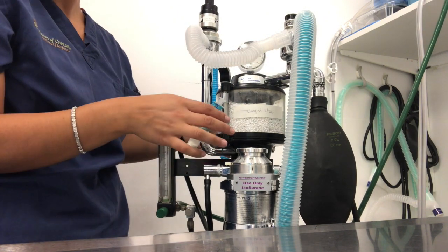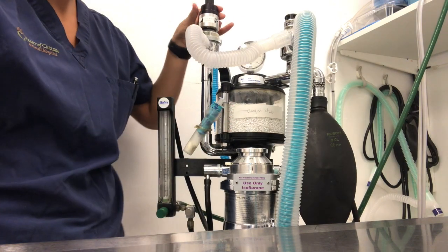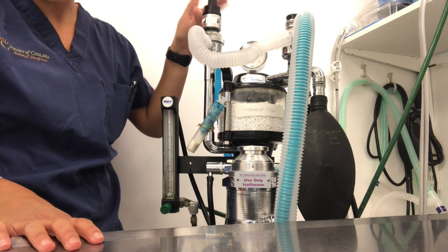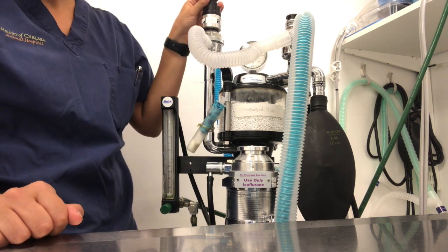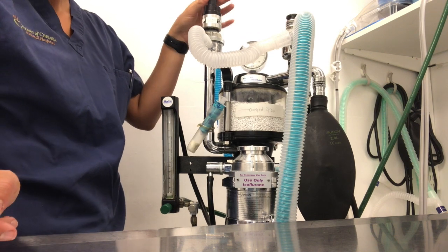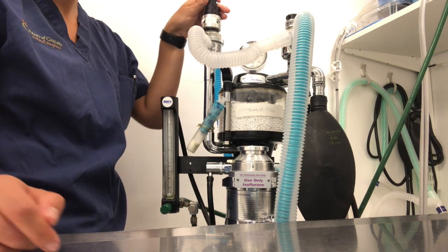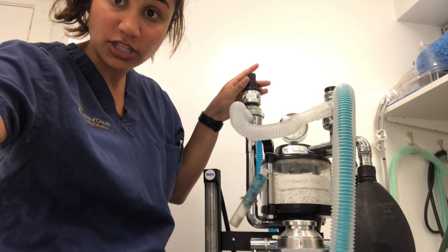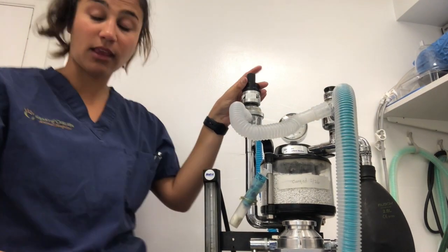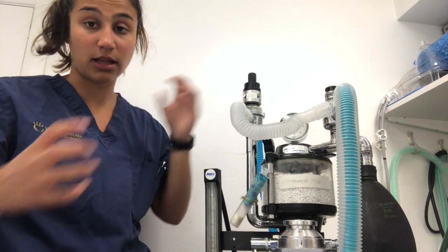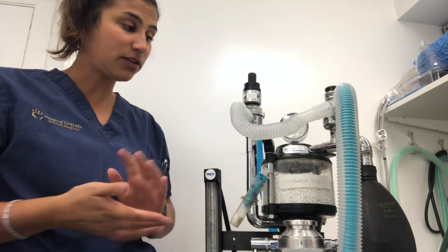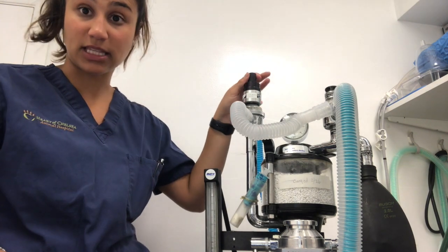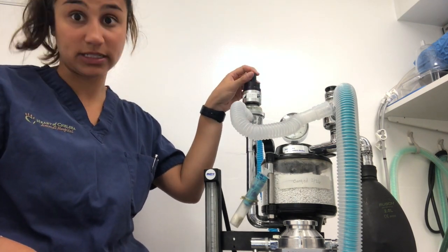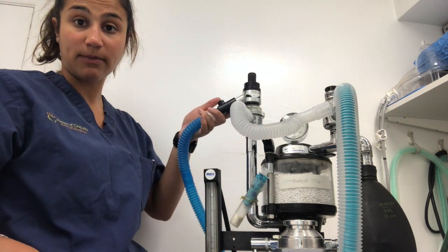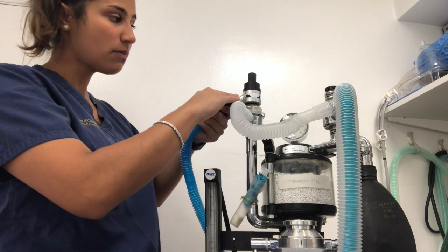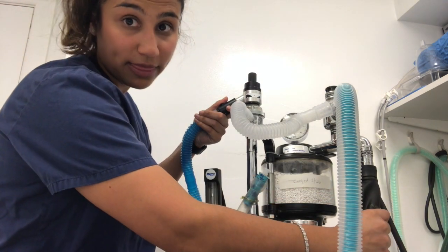The next thing we have is our pop-off valve, which is right up here. Our pop-off valve is a point of exit for anesthetic gases. This valve prevents the buildup of excess pressure from the volume of gases within the circuit. It is very important not to close this valve, because it could send a very large amount of pressure to the patient's lungs, and the lungs can expand way too far. That is very scary. So we always make sure that this valve is open unless it is during manual ventilation. During manual ventilation, we have a button back here, which we hold, and which allows us to give our patient a full deep breath.